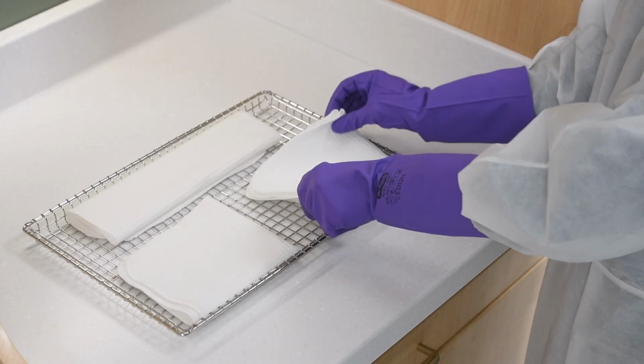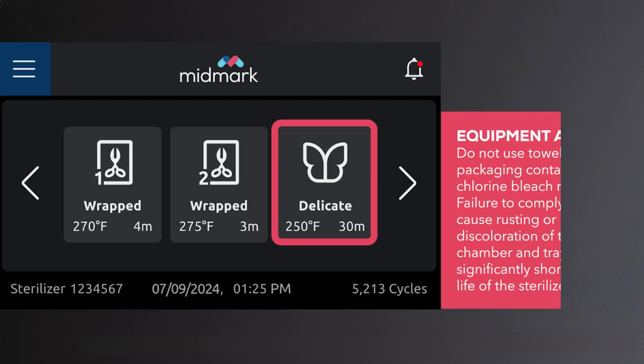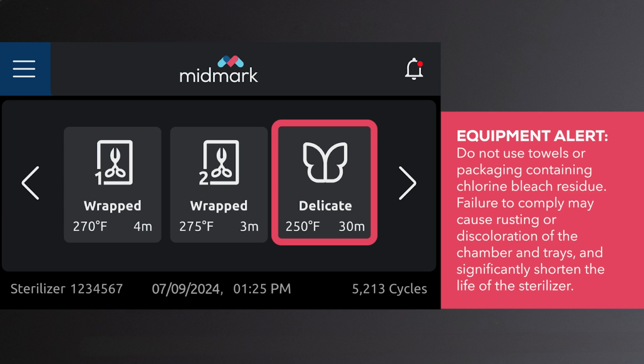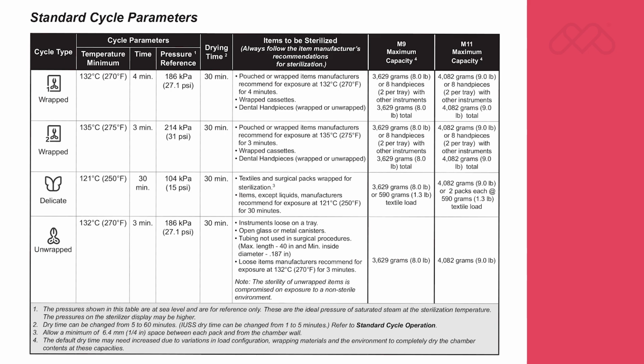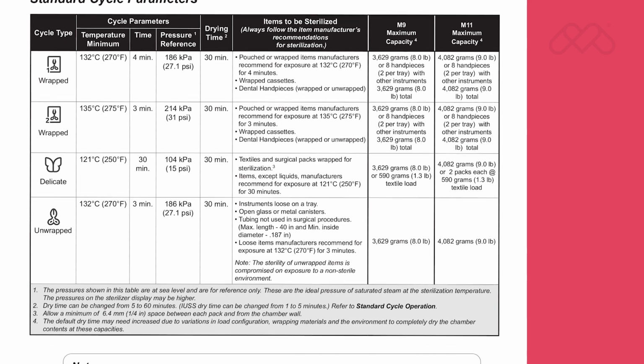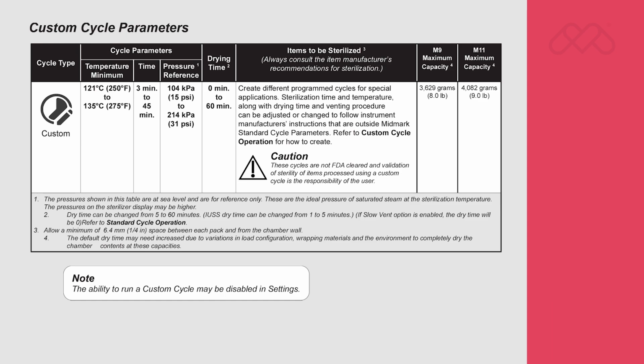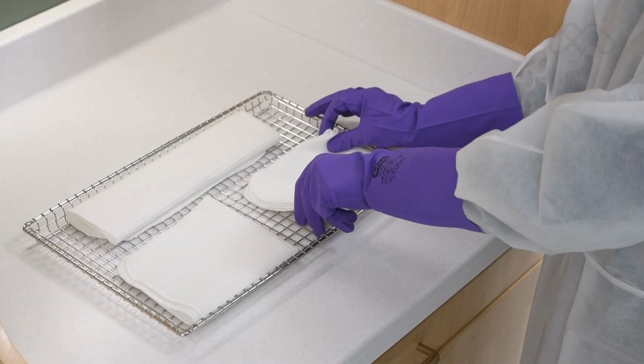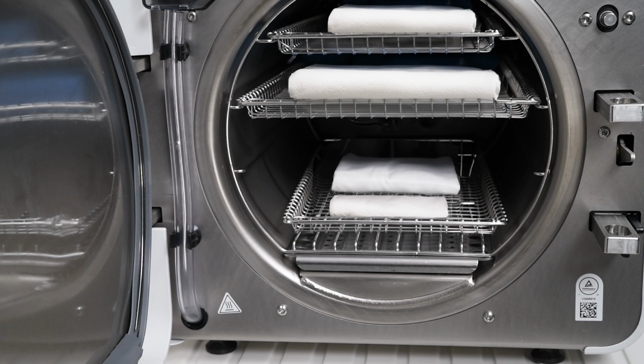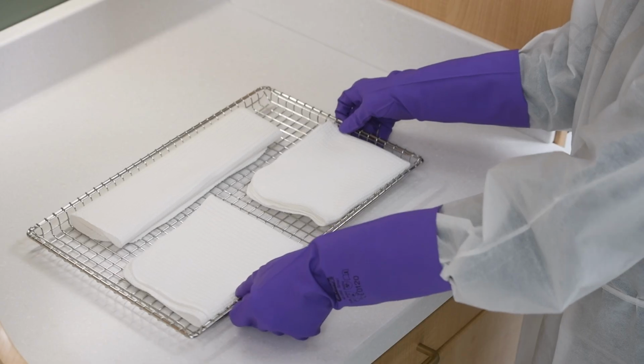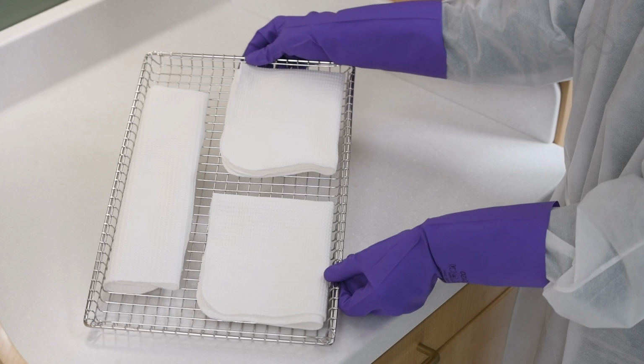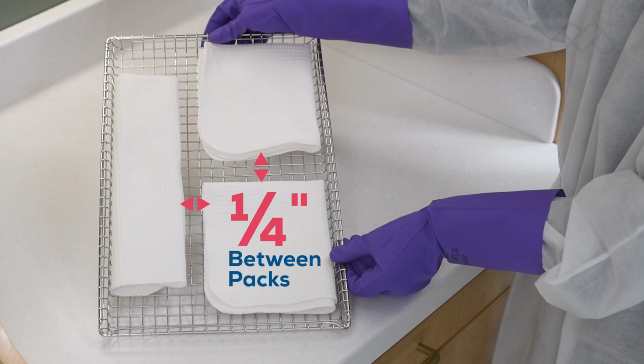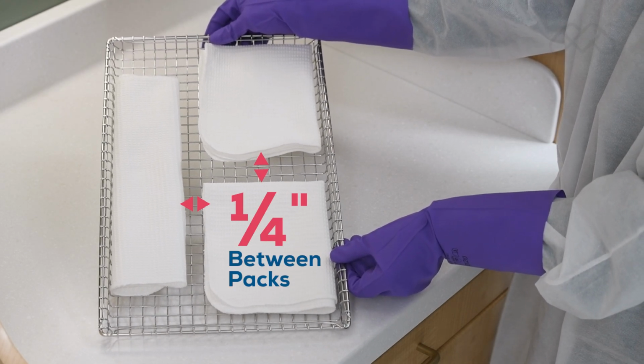Clean textiles recommended for steam sterilization can be processed using the delicate cycle. Verify the acceptability of the delicate cycle sterilization parameters with the textile manufacturer to assure the textiles are compatible. Textile packs must not exceed the thickness limits specified in the maximum capacity tables in the setup and user guide. Textile packs must fit within the boundaries of the sterilizer trays and not touch the chamber wall. If multiple packs are placed on a single tray, maintain a minimum of 1/4 inch between packs for proper steam circulation and drying.